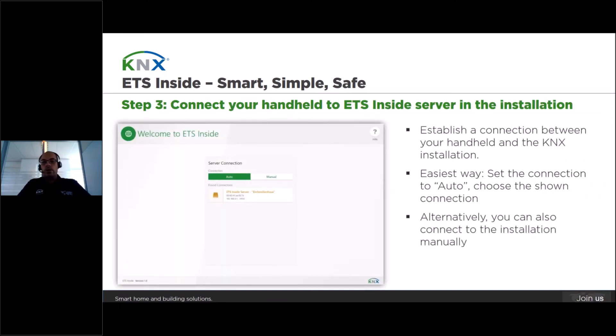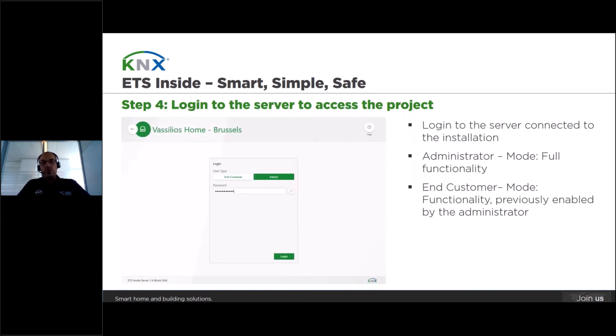In step number three, you have to open the ETS Inside client app and select the ETS Inside server, which should normally be found in the found connections. If for any reason it's not automatically shown, you can always enter its IP address manually by tapping the manual tab. After connecting to the respective ETS Inside server via your client, you will be asked to create a new password if it's the first time. If not, then you have to enter your administrator password.